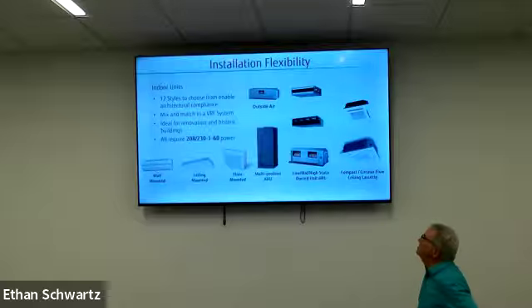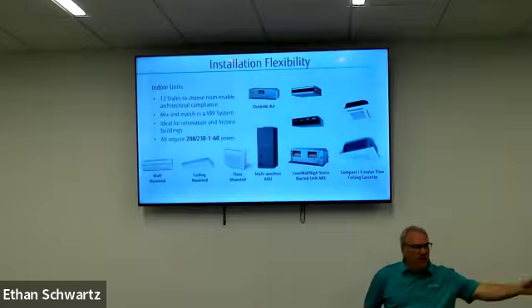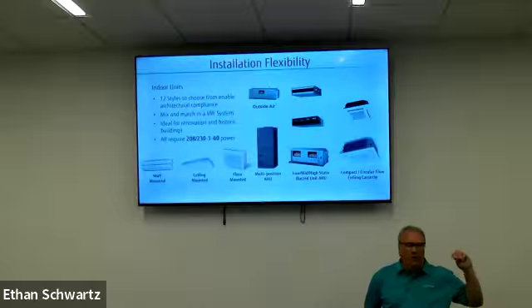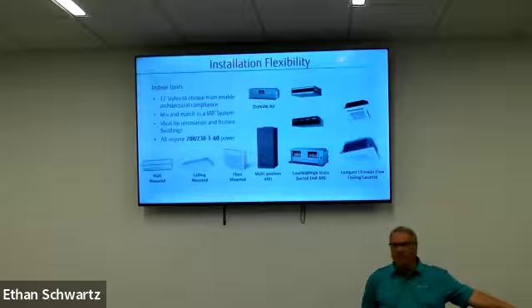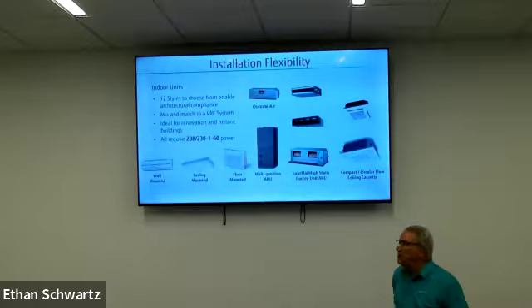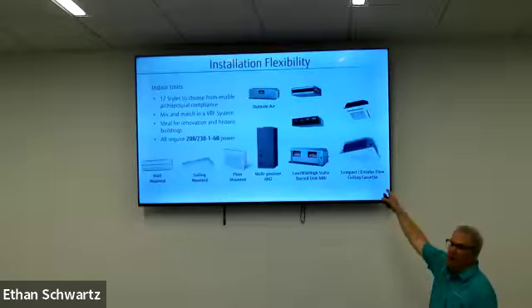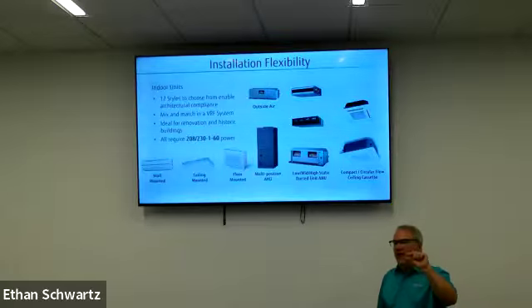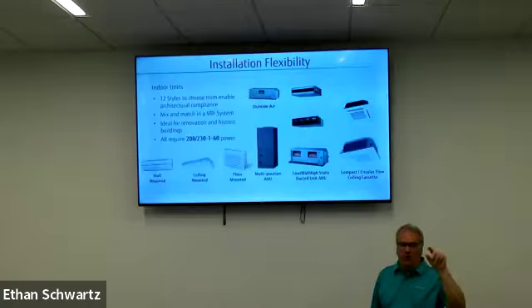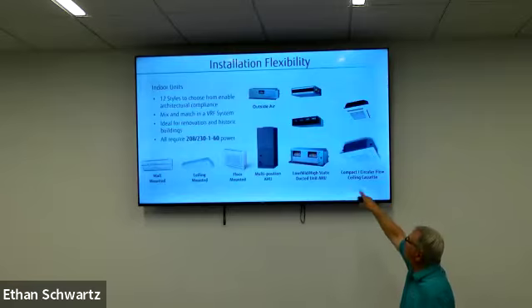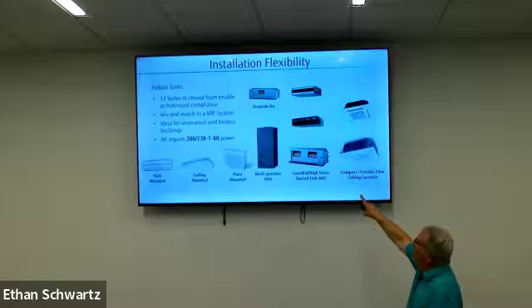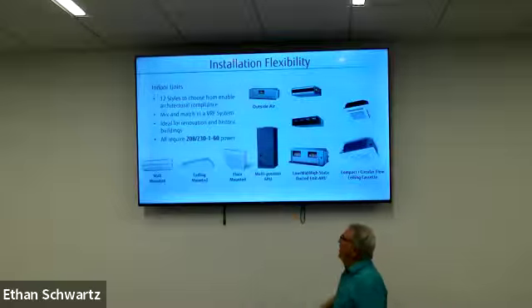So if you have a job that's all cassettes and maybe as supplemental or backup or something, you want to control that valve and open that up so that they get some heat from the existing boiler that's already built into the unit. You need only buy that connector and then probably a third-party relay to make that work. But those are present on all of these units. None of the other ducted have built-in electric heaters, just the multi-position air handler. Does that make sense for everyone?